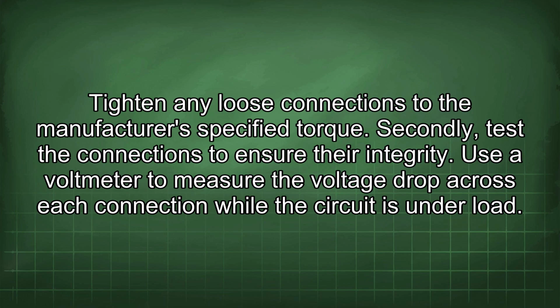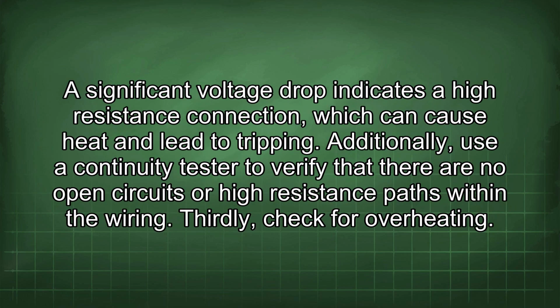Secondly, test the connections to ensure their integrity. Use a voltmeter to measure the voltage drop across each connection while the circuit is under load. A significant voltage drop indicates a high resistance connection, which can cause heat and lead to tripping. Additionally, use a continuity tester to verify that there are no open circuits or high resistance paths within the wiring.